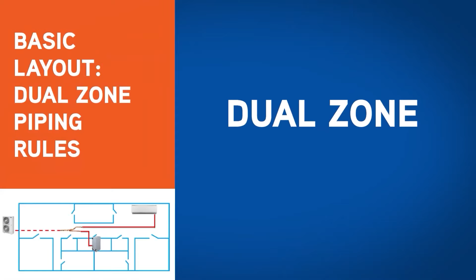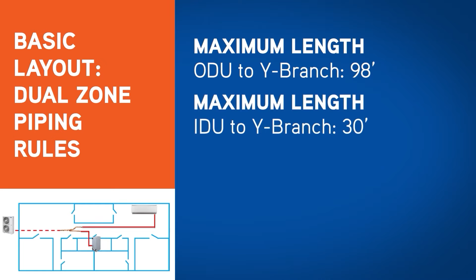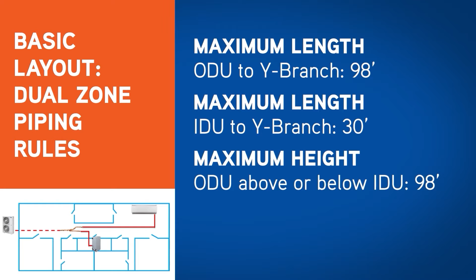A little more complex than the single zone basic layout, the dual zone basic layout has shorter overall line set limitations to keep things simple. The maximum length from the outdoor unit to the Y branch is 98 feet. The maximum length from the Y branch to either indoor unit is 30 feet. The maximum height difference is 98 feet, just like the maximum line set length.